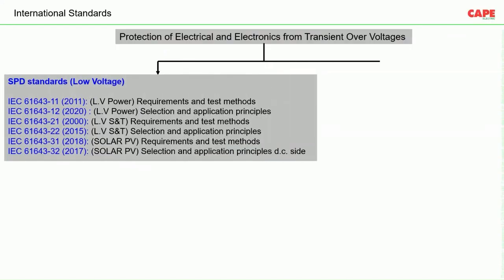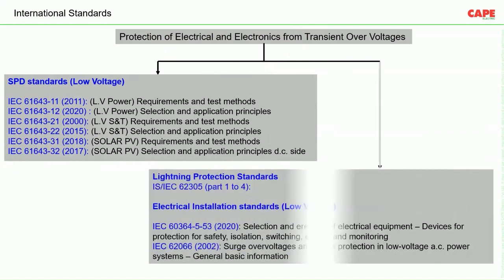First, we are going to discuss the various international standards available for SPDs. These include IEC 61643 Part 11 (2011), which explains requirements and test methods of an SPD; Part 12, which covers selection and application principles; Part 21, which discusses requirements and test methods for signal and telecom SPDs; and Part 31, which covers solar PV SPDs. The first two standards — Part 11 and Part 12 — have been accepted by India as IS 16463 Part 11 and Part 12.